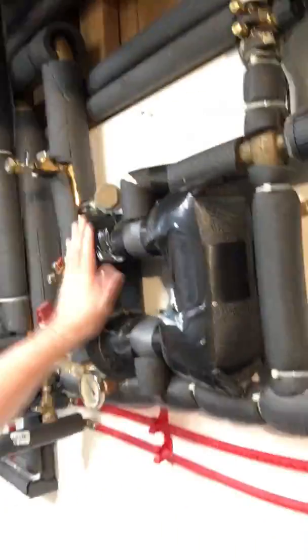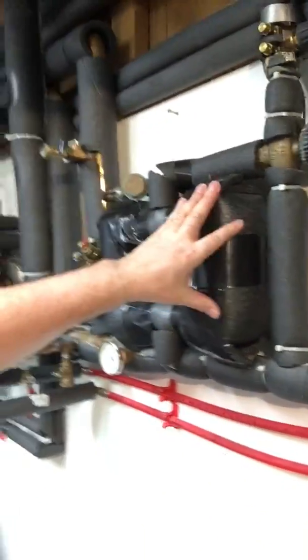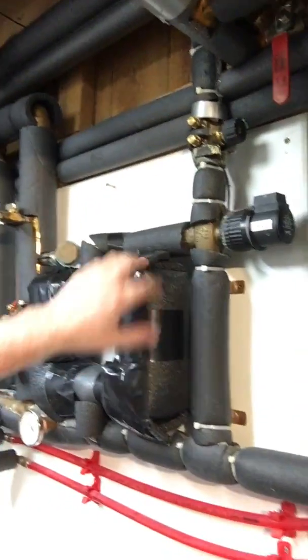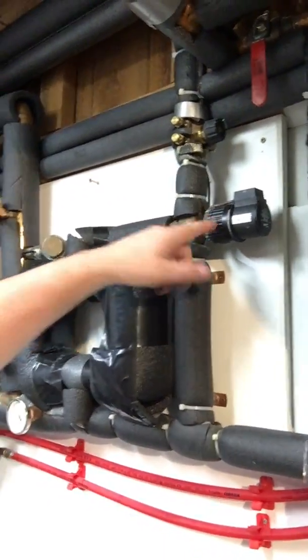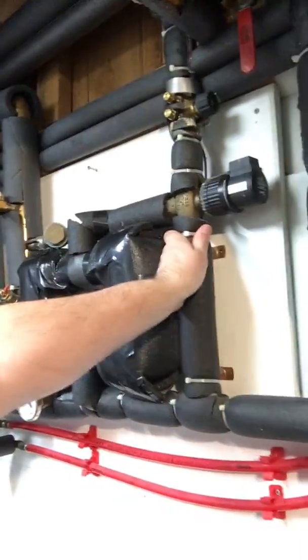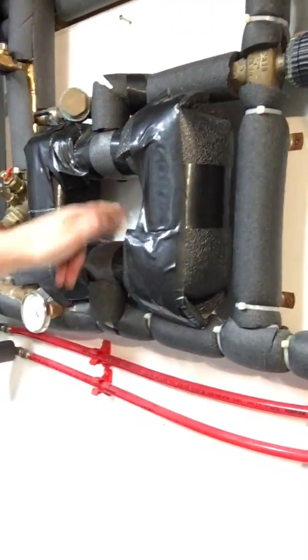So the pool heating is two braze plate heat exchangers, and the temperature is controlled with a set point control, and we just have a diverting valve. So what happens is that when the pool temperature drops, this port closes, forces the water to go through the heat exchangers and then back out to the mechanical system. And it's about a 16 by 32 pool equivalent.